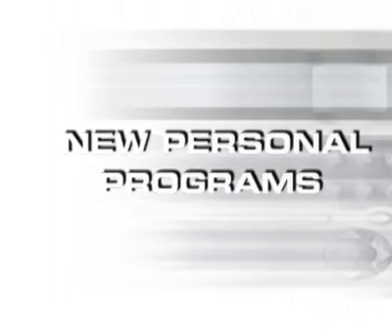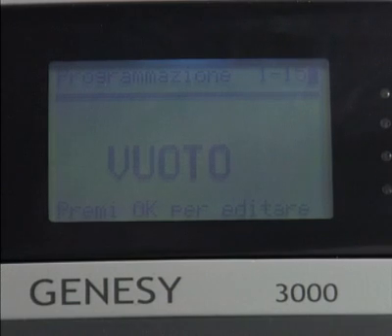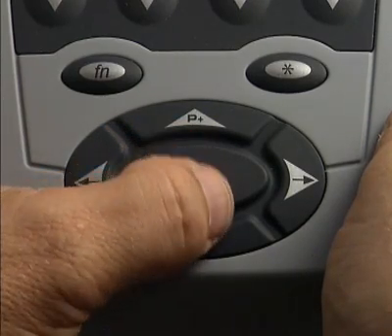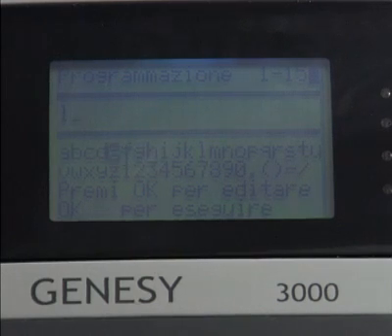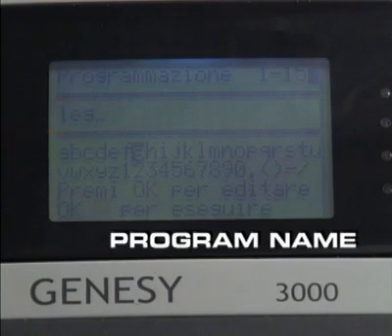One further feature that typifies the professional qualities of the Genesy 3000 Rehab is the ability to program new treatments. Professional users often need to create stimulation programs with parameters specifically selected to meet a particular patient's needs. This is where a programmable machine like Genesy 3000 provides greater functionality by making it possible to create programs that freely manipulate all parameters.